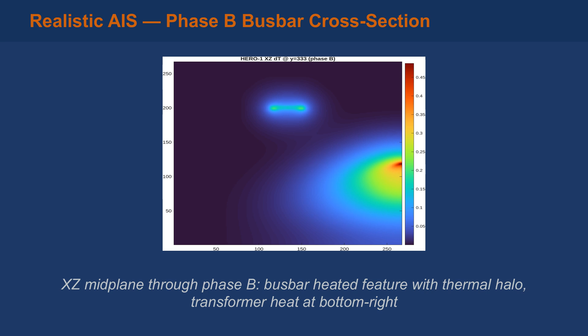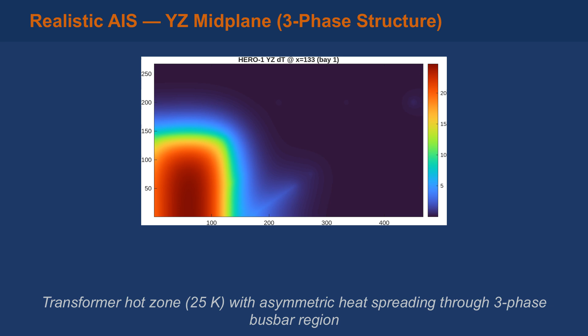The YZ midplane at Bay 1 shows the full interaction. The transformer hot zone of 25 Kelvin at the lower left, and heat rising through jumper connections toward the 3-phase busbar region above. The intercomponent thermal coupling is directly observable.